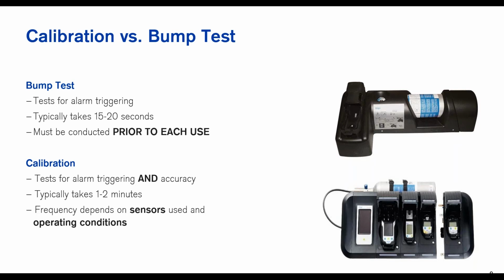And so again, it's checking for the triggering of the alarm itself and the accuracy. It takes usually 1 to 2 minutes. They're all a little bit different depending on what meter you have, but it'll walk you through that. It'll time you down, and you can watch the readings on the display, and it'll show you. And so if you use something like the docking stations you see here, it's almost fail-proof. You just put it on there, it'll walk you through the whole process and does all that for you. But you can also manually calibrate it yourself. If you wanted to take that cylinder off, get a different regulator, and then attach it to the meter, you can do it that way as well.